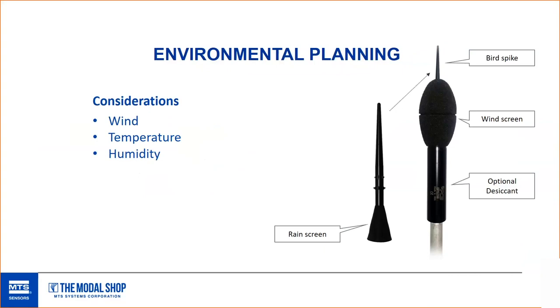There's slots where you can add desiccants into the EPS2116 body to soak up moisture, humidity, and condensation, basically to keep the electronics dry and moisture off the diaphragm. And then there's even preamps like the PRM2103 that has a heater built in, with a temperature and humidity sensor integrated into it. Depending on your humidity content and the temperature, it will kick that heater on to essentially keep condensation away from the microphone and the system.